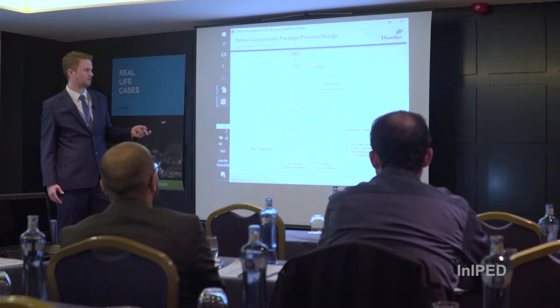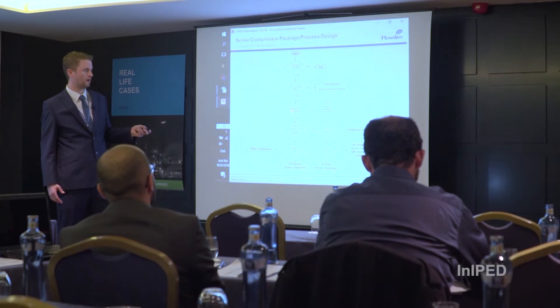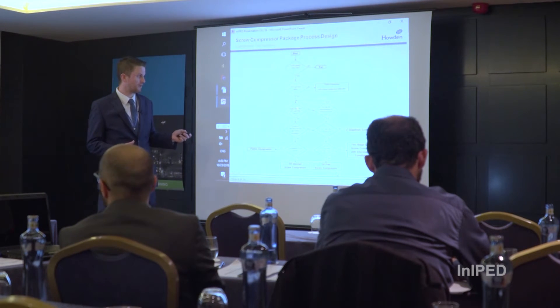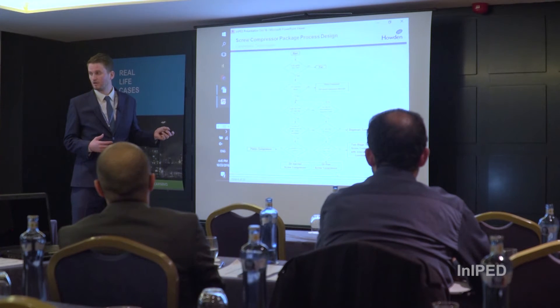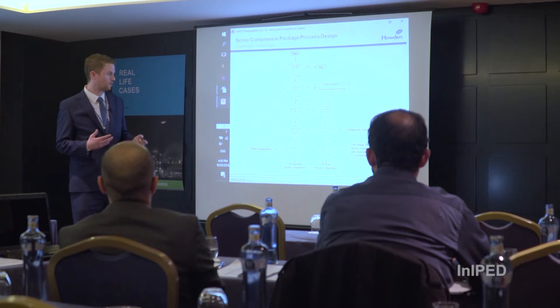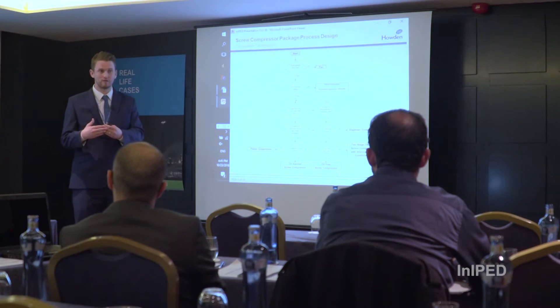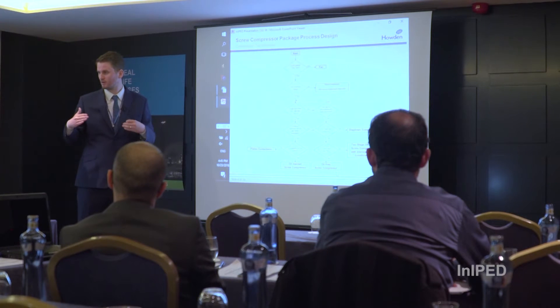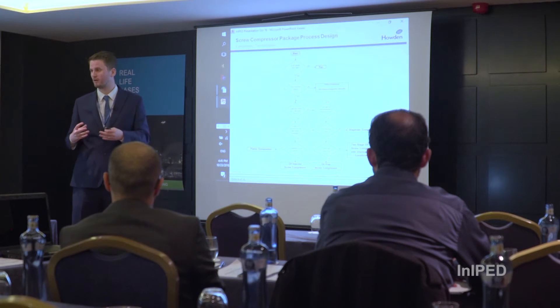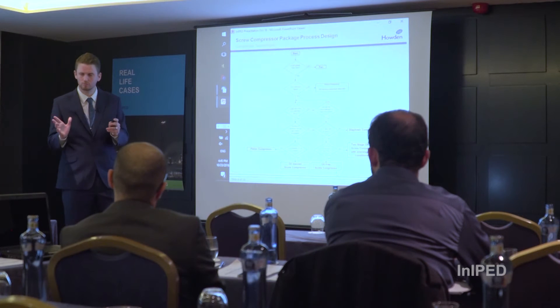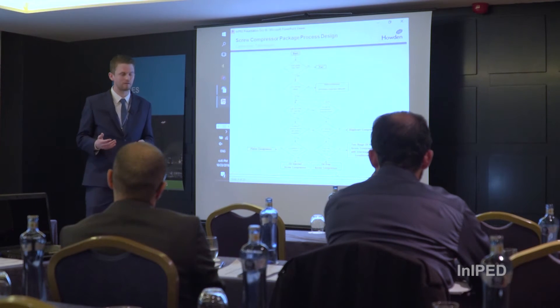So it says here: is the gas dew point at P2 — i.e. the compressor discharge flange — less than 100 degrees Celsius? That's really key, because oil-injected screw compressors require a difference between the operating temperature and the dew point of at least 10 degrees Celsius, to prevent any contaminants in the lubricating oil sent back to the compressor. But we'll discuss that in more detail later.